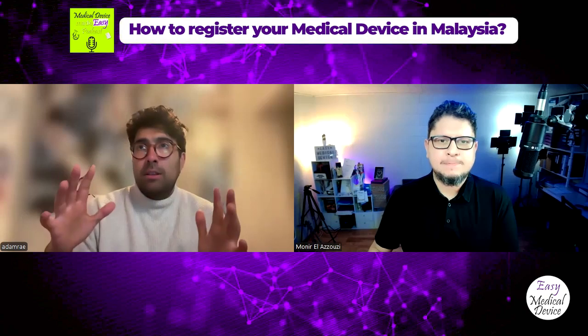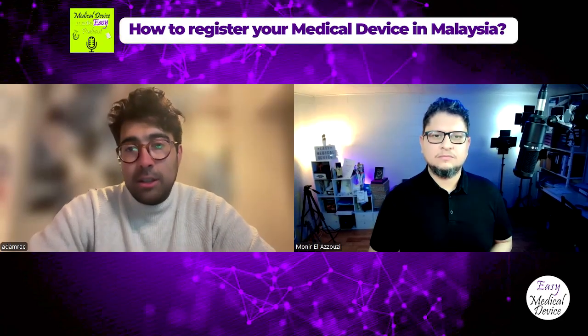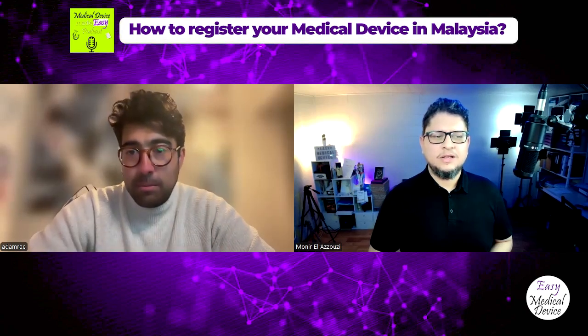Yeah, so in theory, the directive is the same. They have a harmonized template for a technical document, the common technical dossier template, which is the kind of 'everything needs to be in here' format. Individual countries still require their respective registration, so not like EUDAMED. This is maybe a good opportunity to call out to the Malaysian Medical Device Authority and the Association of Southeast Asian Nations to say how much they would benefit from a single registration point. It would be a big change for that region. At the moment they can all apply the legislation, it needs to be national law, and then individual registrations are required. But the requirements are the same essentially, and then there are just little tweaks, like what we had in the EU before MDR and IVDR.